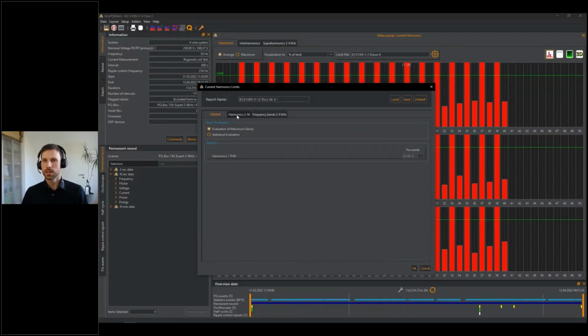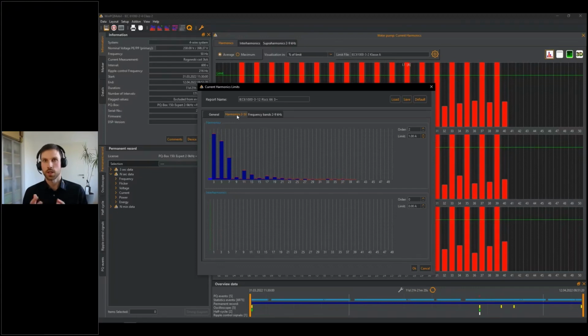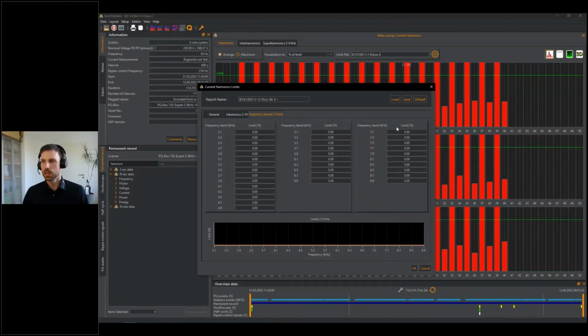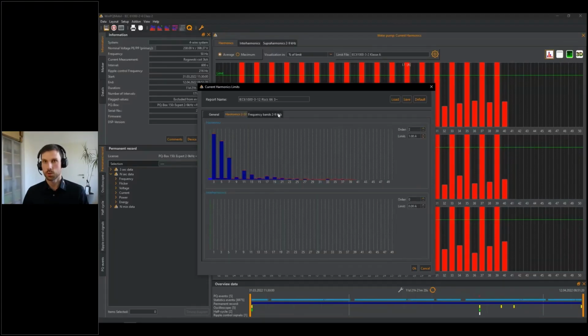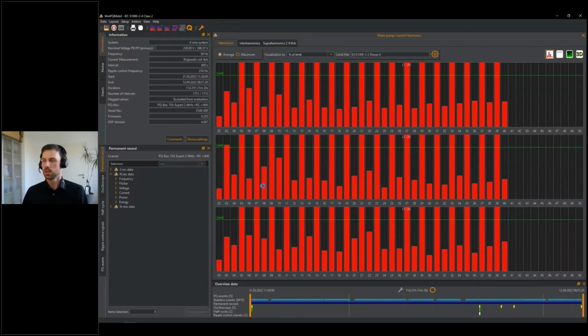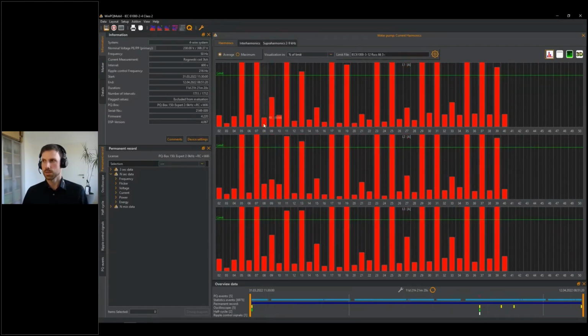And if I have special conditions or an individual contract and individual limit values, I can adjust every single limit value in here up to 9 kilohertz. So this is possible. For example, for the third harmonic, 25 amps, I can set an individual limit value and go as I wish for each individual harmonic or interharmonic. So I confirm with OK. And now the evaluation changes. I see, okay, I'm still above the limit values.